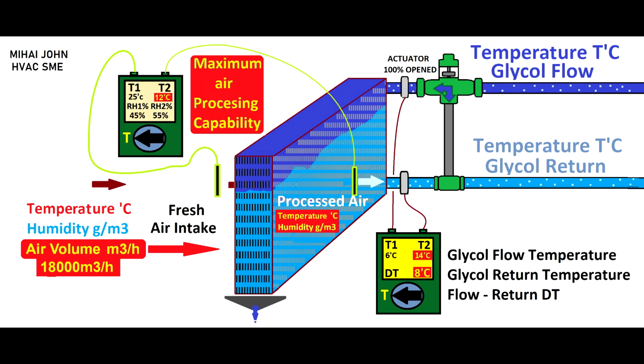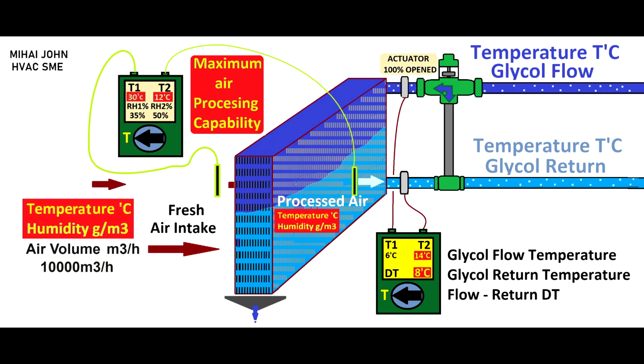If the engineer overseeing the system does not cross-reference the AHU specification, they may erroneously pursue investigation into a potential glycol circulation issue. It is essential for engineers to carefully analyze and ensure that the system modification aligns with the equipment specification to prevent misdiagnosis and optimize performance. The current scenario pertains to the user system requirement specification.